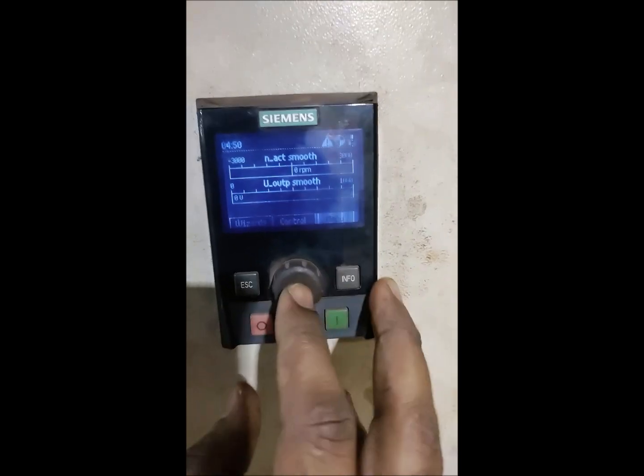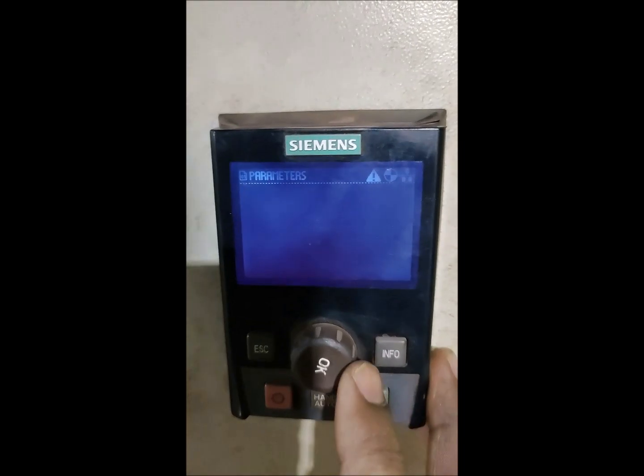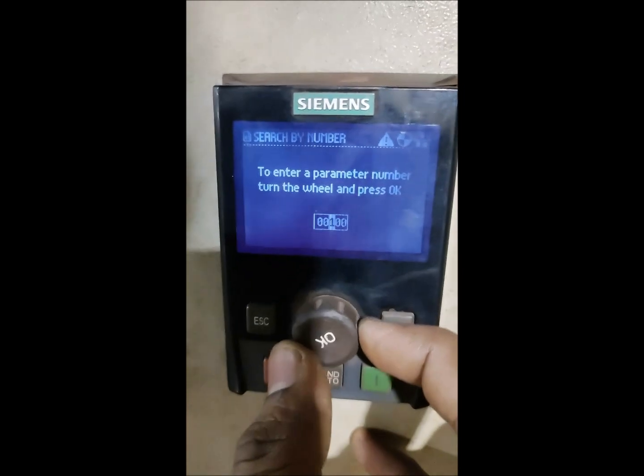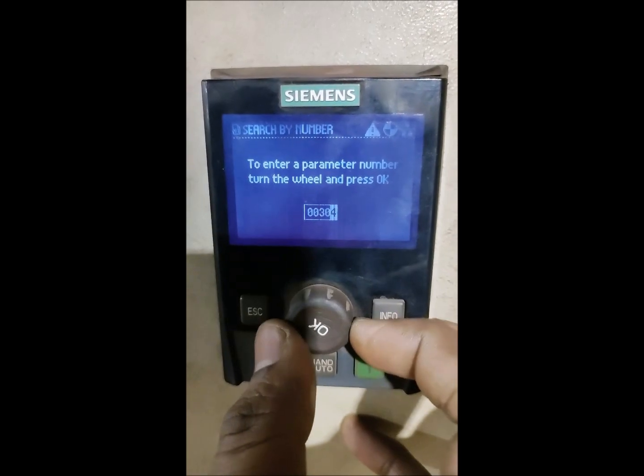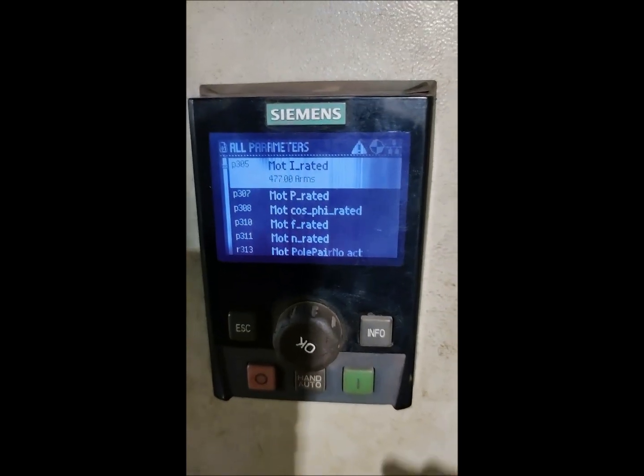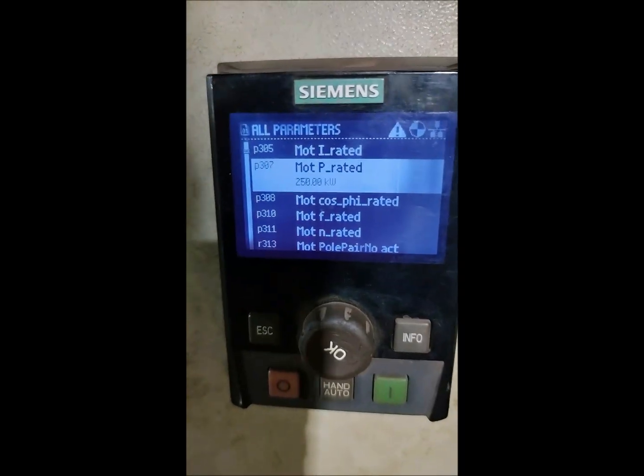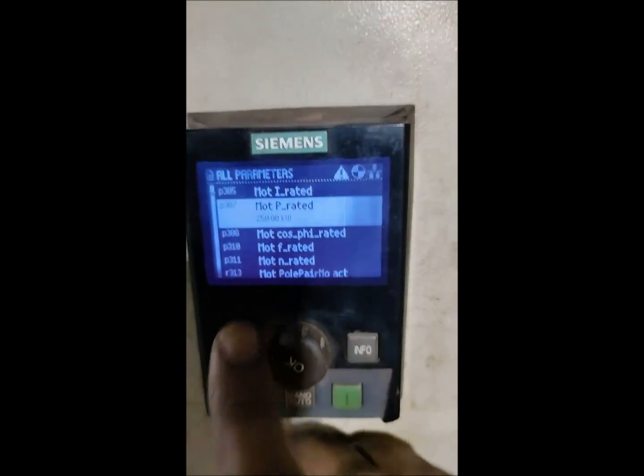Now we'll check the actual parameters that are available on the drive. We'll go to the menu, then parameters. Since all the important parameters are in the 300 series, we'll press 300 here. Better to go directly to 305 to check the current. So this is the rated motor current - 477 amps. And 307 is the motor rated power - 250 kilowatt. So this is the actual power of the drive that we will change as per the application. And that's how the first process has been completed.